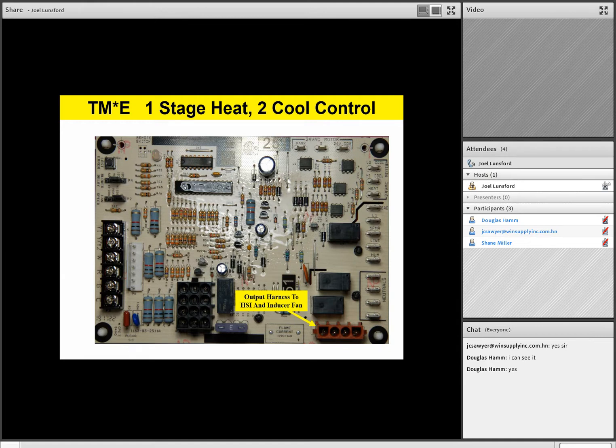Right next to that is a flame current pad. This is a really neat Champion furnace product exclusive. I don't know of any other manufacturer that does this. This flame current pad allows the technician to check flame current right on the board with a voltmeter. Instead of having a special flame current meter, or a meter with flame current capability, this is very, very simple. If you take a look at those two little solder spots, or test points, it says negative and positive. Basically, 1 volt DC on the voltmeter is equal to 1 microamp flame current. And that's pretty cool.